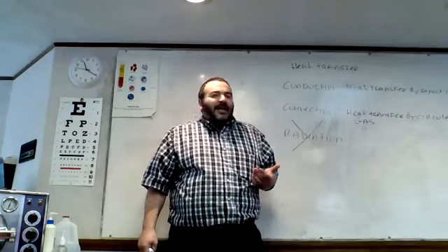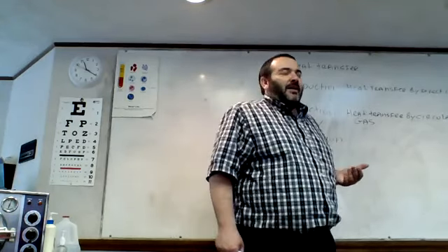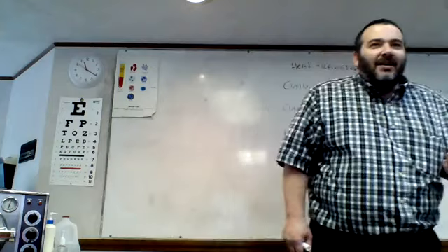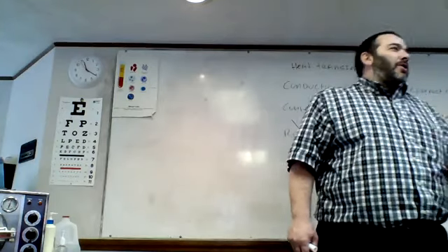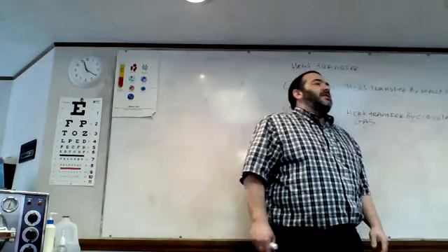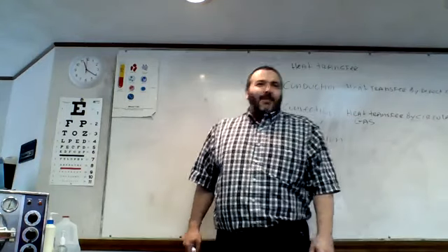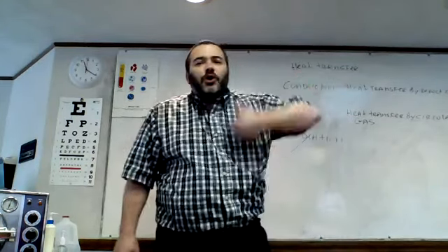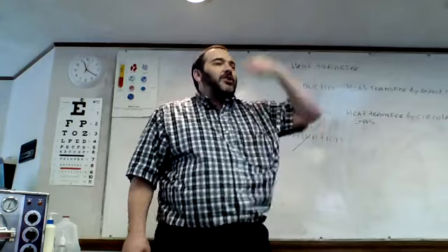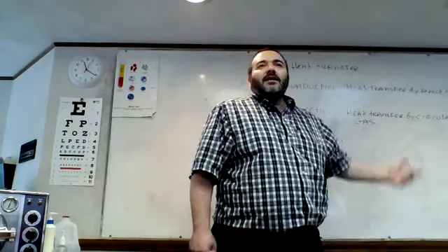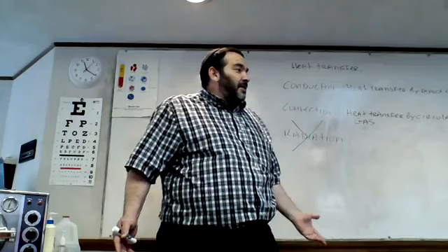Okay? It's like overloading your washer. It's like overloading your dryer. You may have gotten the door closed, but it's just not happening. You're going to take out dirty clothes. The same thing here. The air needs to circulate freely around the packages. If it doesn't penetrate. Right?